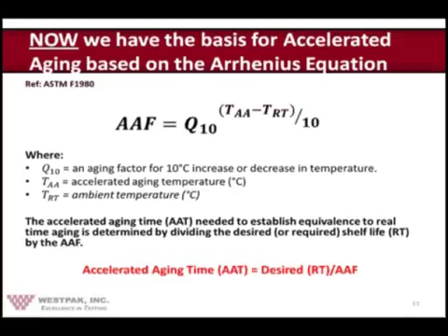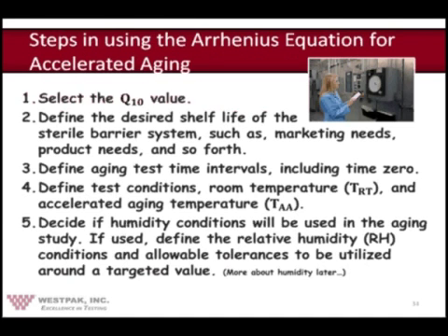So let's take a look at how that's done. I've selected 10 steps by which this process is actually used in what I'm going to call the real world, or how we actually do it when we go about aging medical devices. First of all, we select the Q10 value. Now how in the world do you do that?